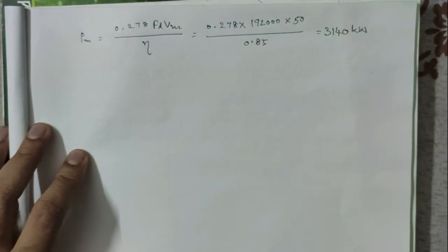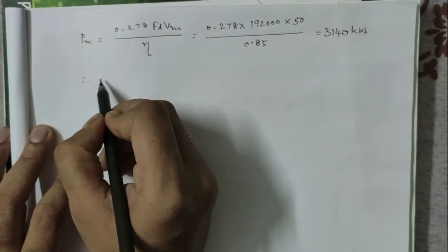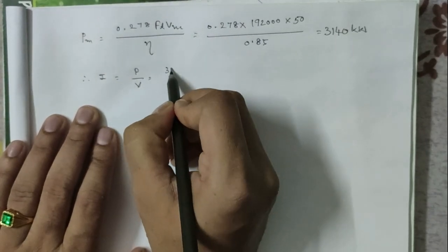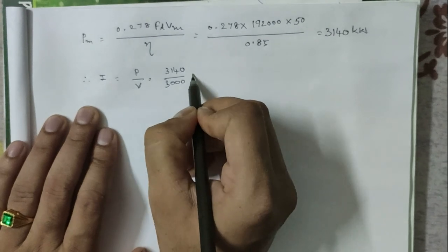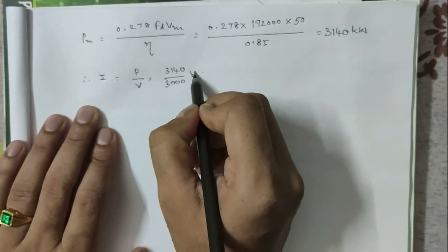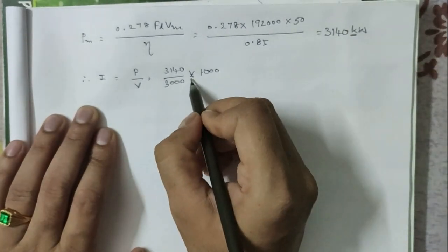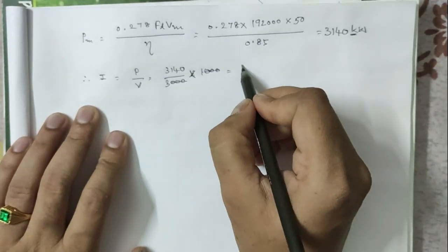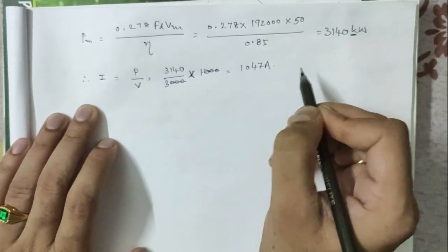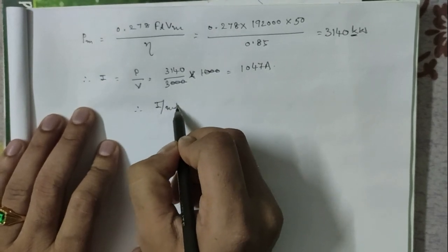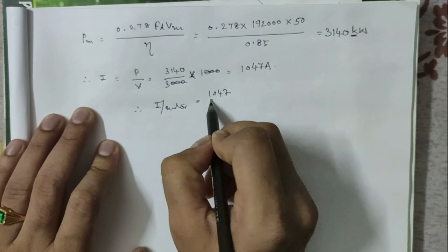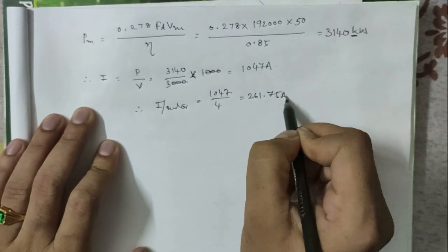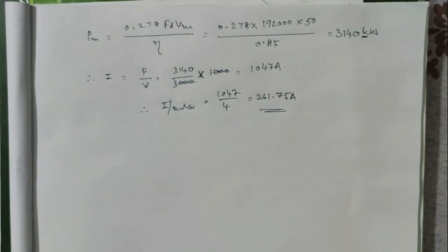The power comes out to approximately 3140 kW. The current drawn is I = P / V = (3140 × 1000) / 3000 = 1047 amperes. Therefore, the current passing through each motor = 1047 / 4 = 261.75 amperes.